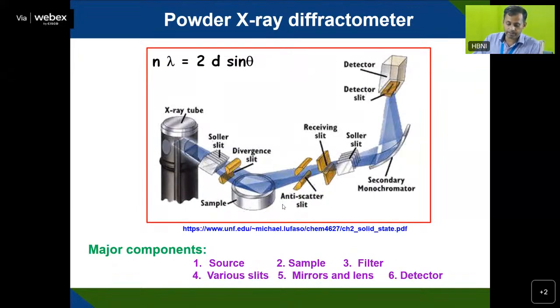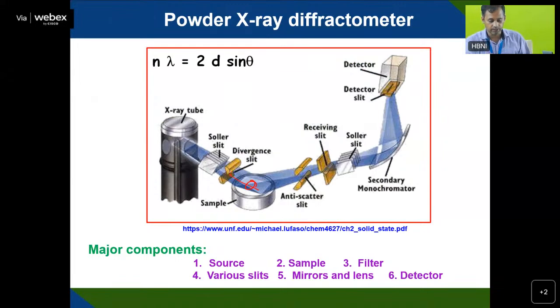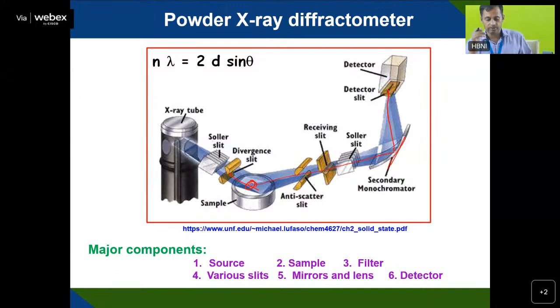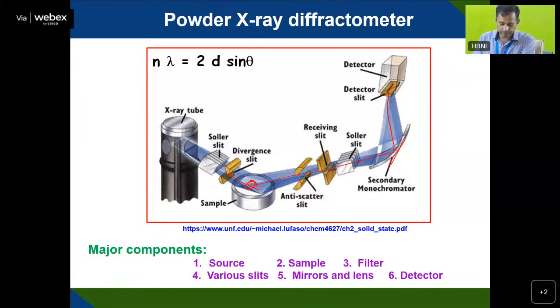This is a schematic diagram of a powder X-ray diffractometer. There is an X-ray tube as the source, a sample stage where the sample is kept, and the X-ray passes through various slits — Soller slits and divergence slits — falls on the sample, then passes through more slits to a secondary monochromatic mirror, and finally to the detector. Major components are: source, sample, filters to separate K-beta from K-alpha lines, various slits and mirrors, and detectors.